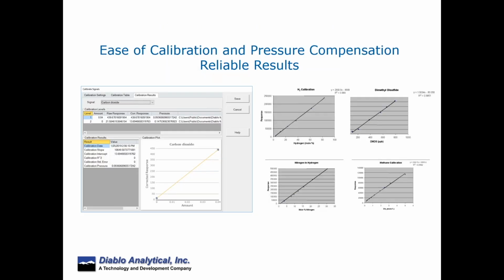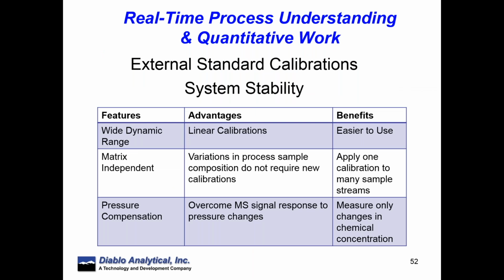The calibrations are very linear with this interface and with the mass spectrometer, typically 4 orders of magnitude. And we've shown 4 examples here, including hydrogen. Hydrogen can traditionally be more challenging for a number of mass spec systems. You can see you get a nice linear calibration curve. So with external standard calibrations, we have a wide dynamic range, linear curves, and we have matrix independence, so that as you have changes in your process or as you go from calibration to process monitoring, you can use the same response factors, same calibrations, and we have pressure compensation.